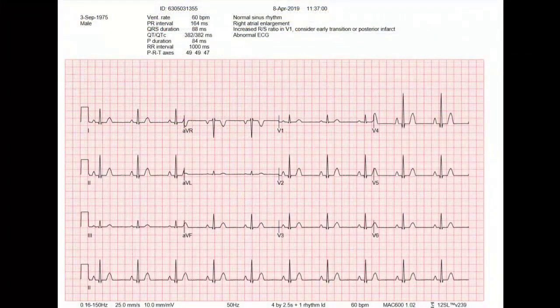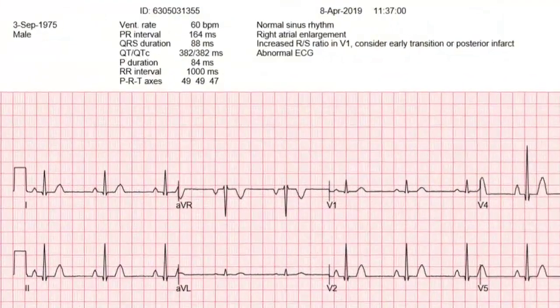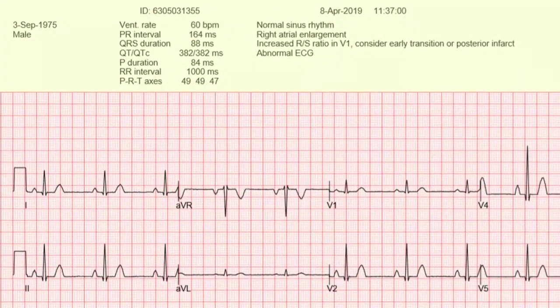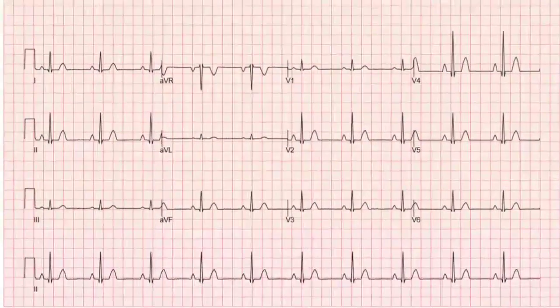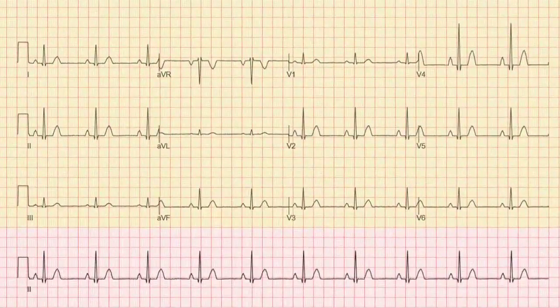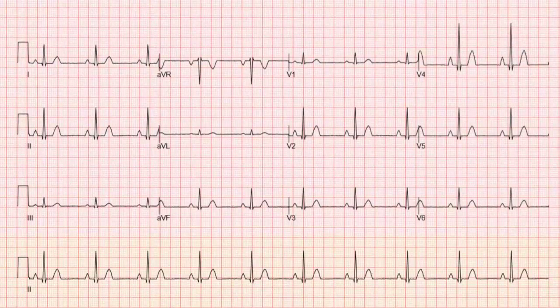The report contains the patient's details, the average measurements and the system interpretation with a standard resting ECG report format. Beneath this is 2.5 seconds of every lead view with a 10-second rhythm strip of lead 2 along the bottom.